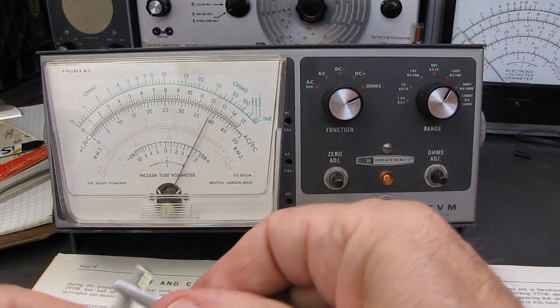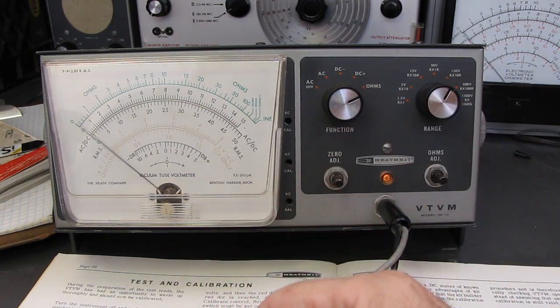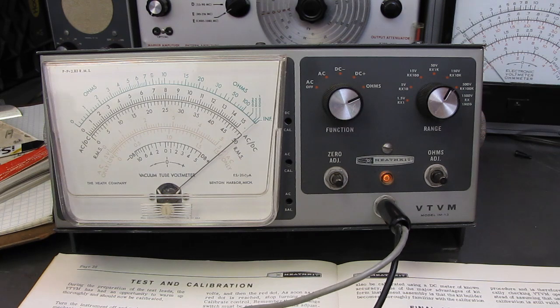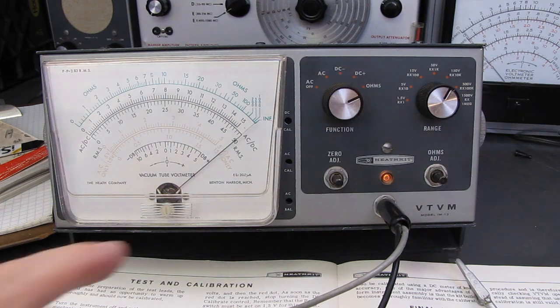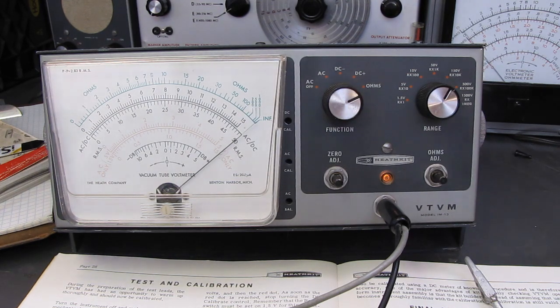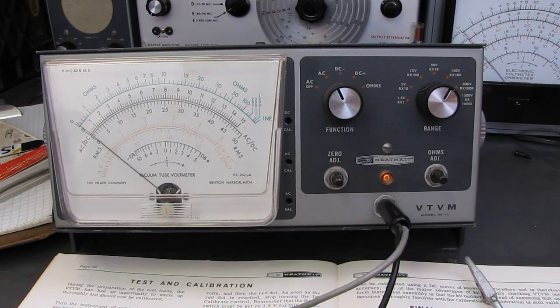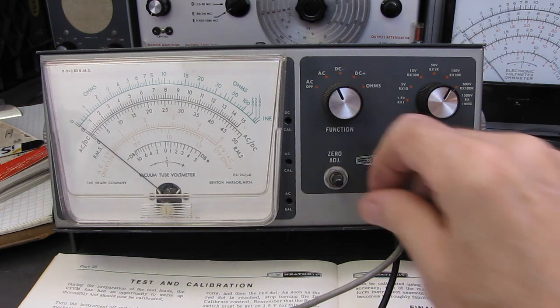I am on AC ohms. And the ohms adjust. And the check for that is to check both ends of the range. And make sure it'll zero and go up to infinity. Everything else is set by the resistors inside the meter. So as long as the resistors are in cal, haven't been burned up or in tolerance, the meter is good.